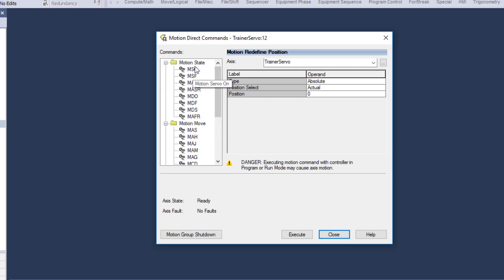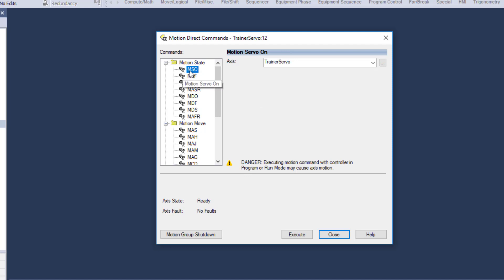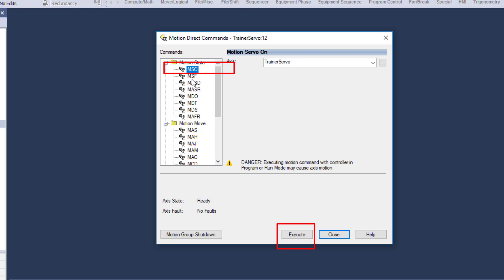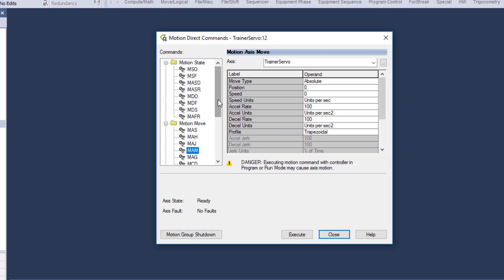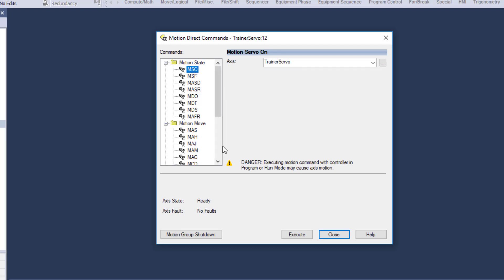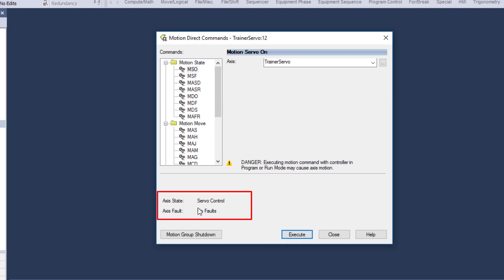If you're in this environment, before you run the servo you have to be able to turn it on. In the natural order of operation on servos, you turn the servo drive on, which closes the loop. Once you close the loop, you have the ability to do a jog or a MAM and move the motor — but first you have to cut it on. You can see the servo drive is in axis state, it's on, it's in servo control.